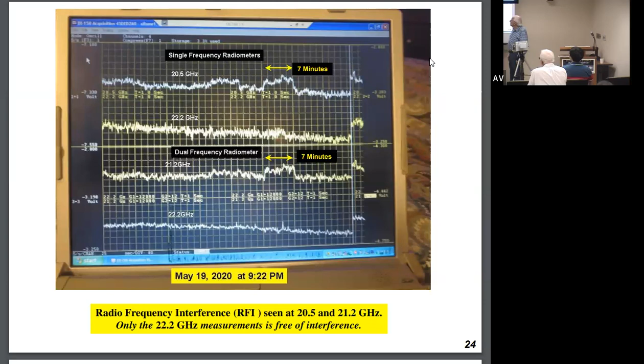So there's that RFI that you're seeing at those two frequencies. Those two frequencies obviously are not good. I don't have a 23.8. I can't build one, so I can't check that. But that's what I've been seeing. The instruments work beautifully when you don't have RFI. That's this 20.5 right here. But once you have RFI, you really have problems. So I said, well, is there any way to deal with it? Here's how you deal with it, at least one way.